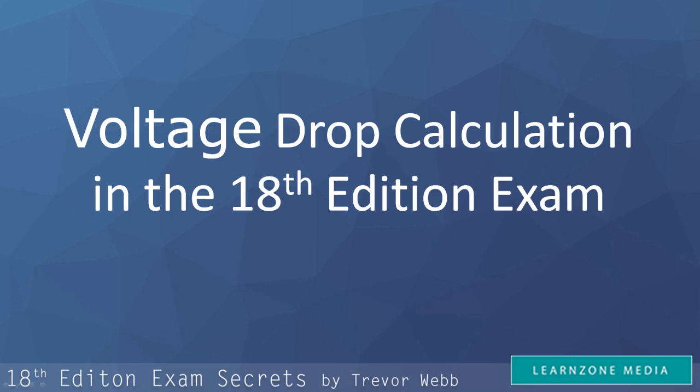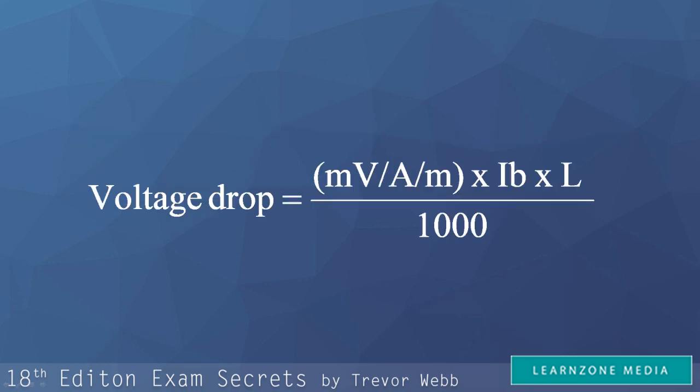The first thing that you need to know is the formula for voltage drop, which is voltage drop equals millivolts per amp per metre times IB times L divided by 1000. This is not mentioned anywhere in the book and that is exactly why I recommend making a note of it in the book right now.